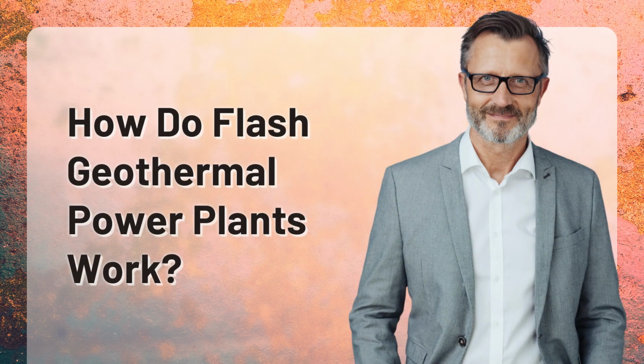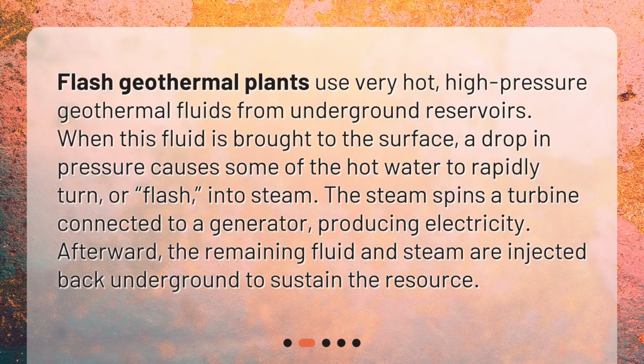How do flash geothermal power plants work? The flash geothermal plants use very hot, high-pressure geothermal fluids from underground reservoirs. When this fluid is brought to the surface, a drop in pressure causes some of the hot water to rapidly turn, or flash, into steam. The steam spins a turbine connected to a generator, producing electricity. Afterward, the remaining fluid and steam are injected back underground to sustain the resource.